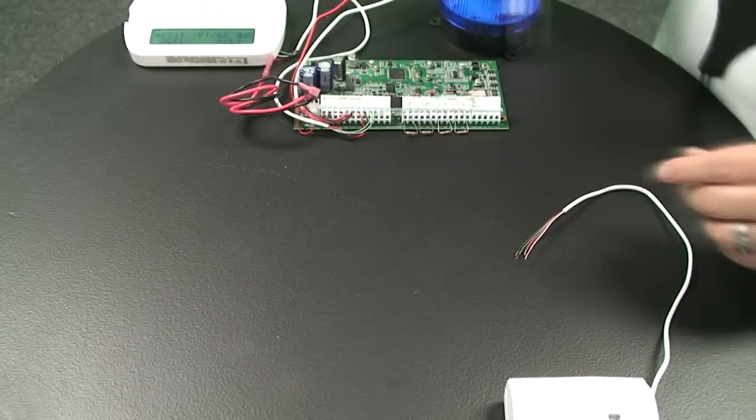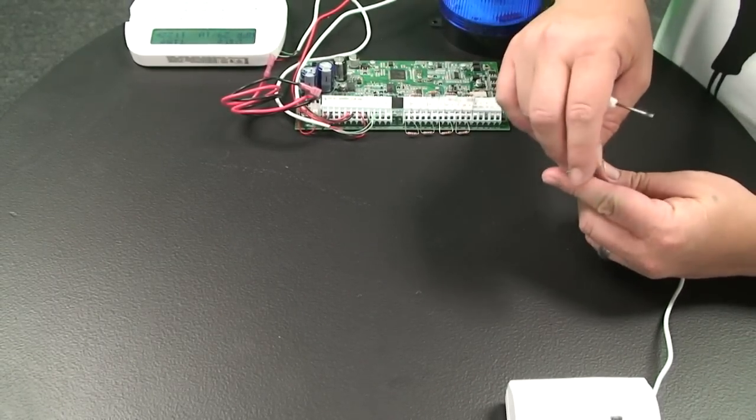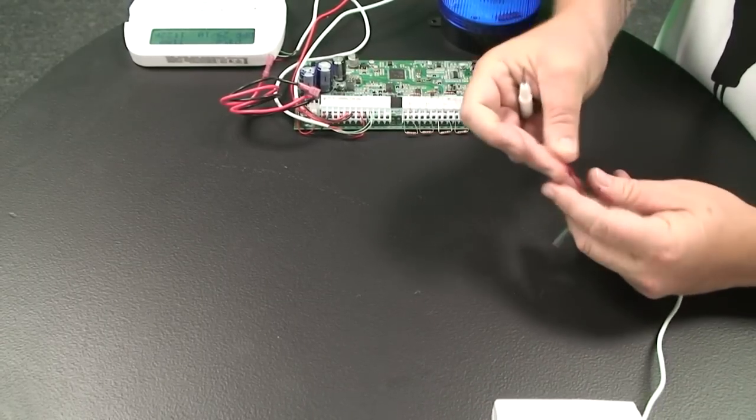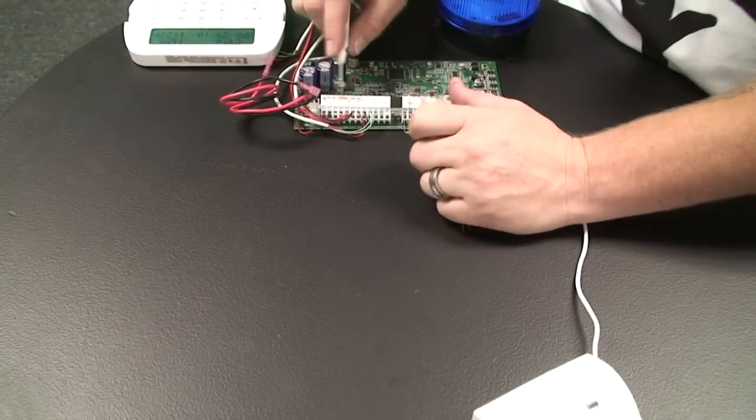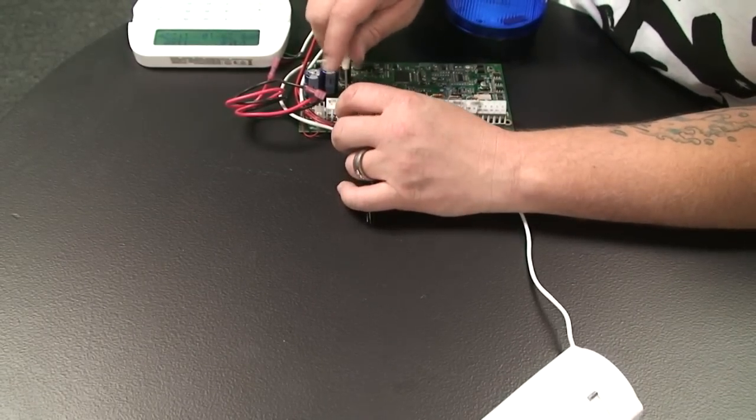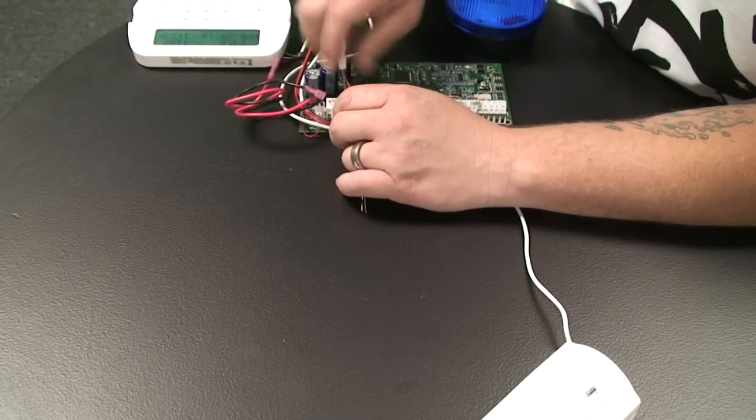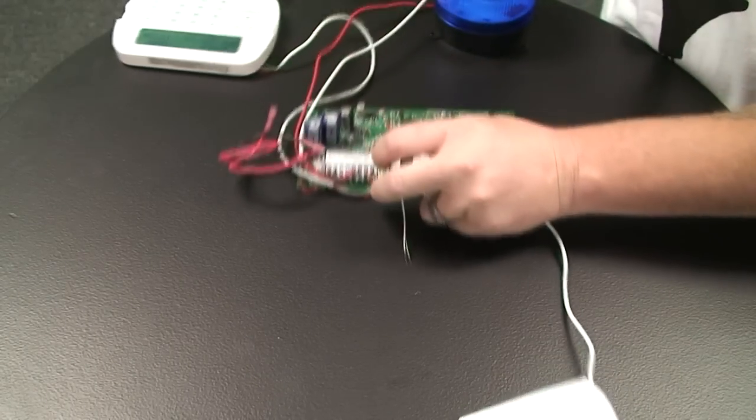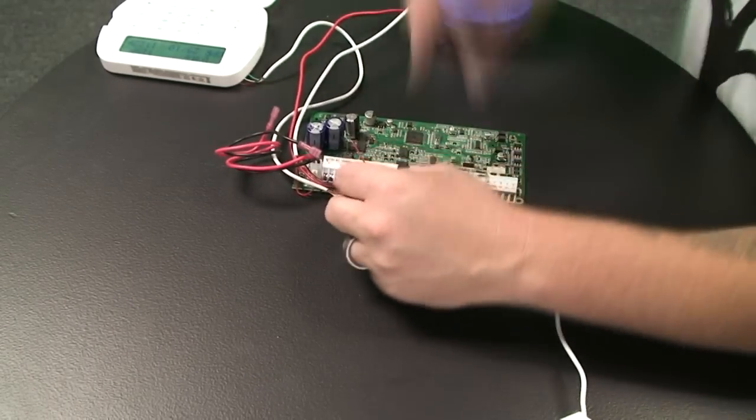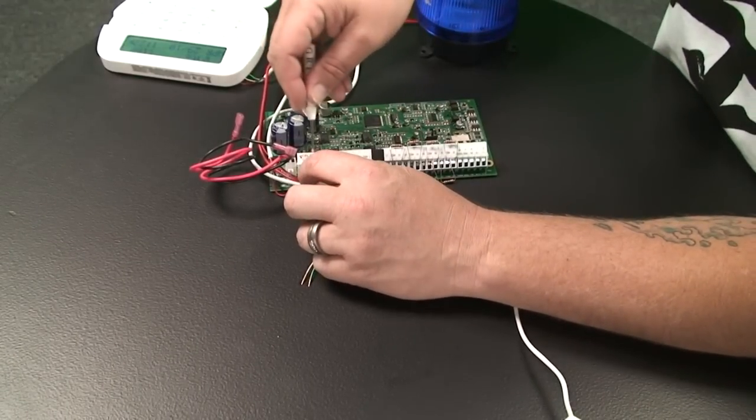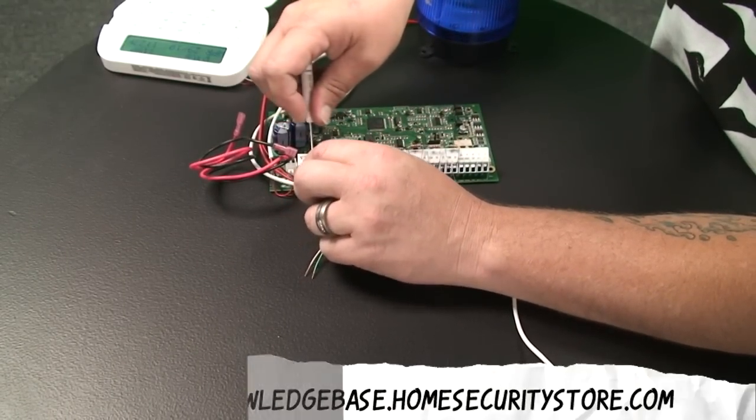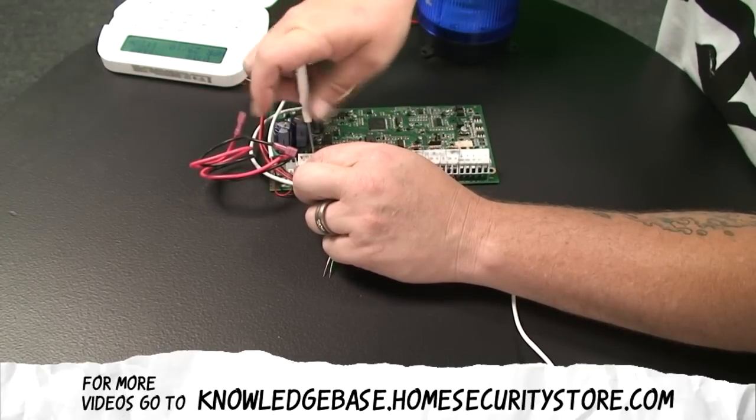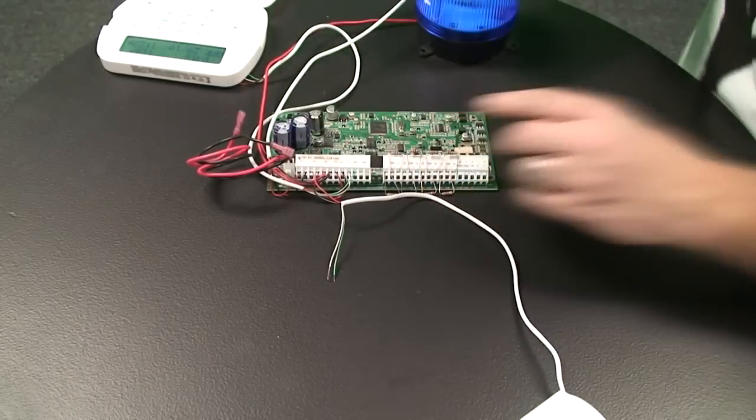What we have here is we need to get our power from the control panel which is 12 volts DC. So we're going to take our red and black wire here, and we're actually going to get it off the auxiliary plus and minus circuit. So we'll take our black wire and put that into auxiliary minus. And then we'll take our red wire and put that into auxiliary plus.